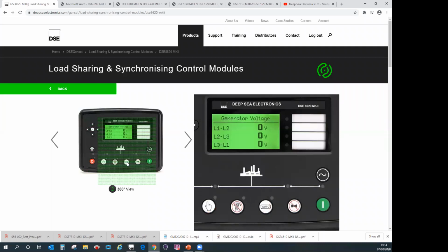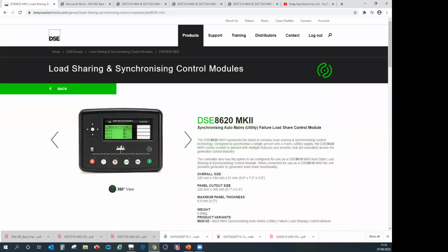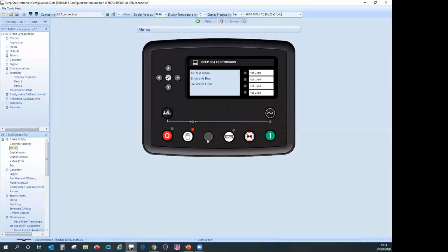It's primarily designed for a maintenance person, like a caretaker, who perhaps isn't a generator specialist or engineer, but whose job is just to make sure the generator runs. Rather than pressing the stop button, the green button, the breaker close button, the breaker open button, and putting it back in stop mode, you simplify it by using the test button. On the 8610, because it's not an 8620, it doesn't have the test button, so you can just leave that button blank, but you can actually utilize it for other things. You can use it in what's called the module's inbuilt PLC, and you can use that button for whatever you want.